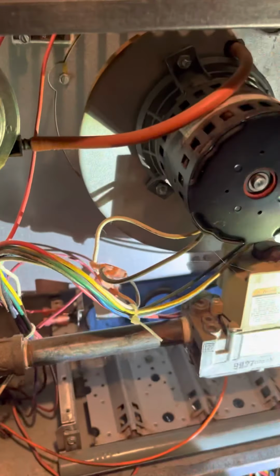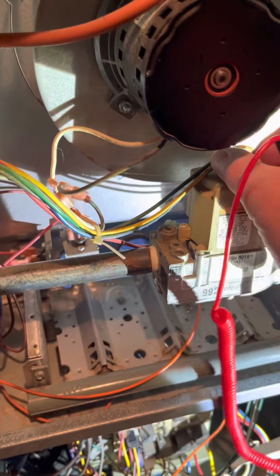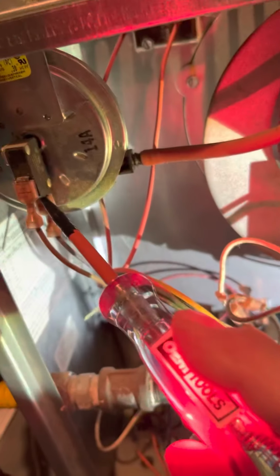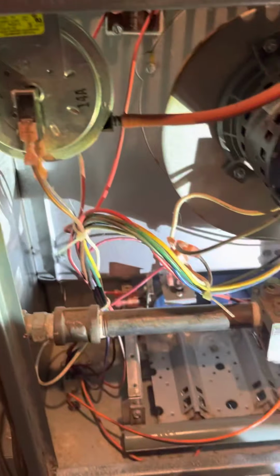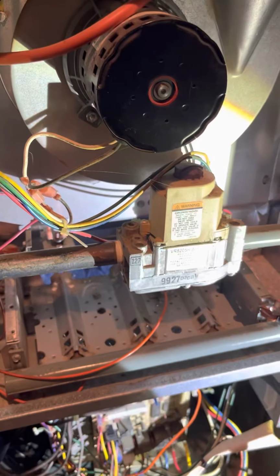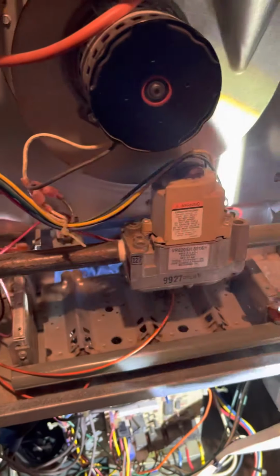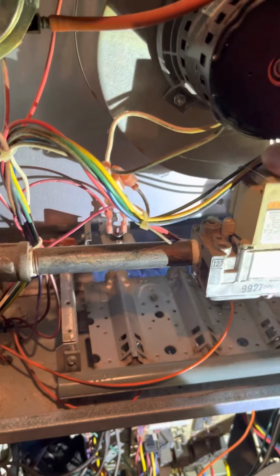See, I have 24 volts here, and I have 24 volts in here, over here. I can't reach it. There's 24 volts there. My main limit up here, see, 24 volts and 24 volts on both sides of it. If one side didn't have it, then I would know that there's something wrong with that switch. Just like right here, I have 24 volts coming into this pressure switch, and I have 24 volts coming out. Or I don't know exactly how many volts. I'm using a light, but you can tell if it's real dim, it's not 24 volts. And then you would go and get your voltmeter out and test it from there.